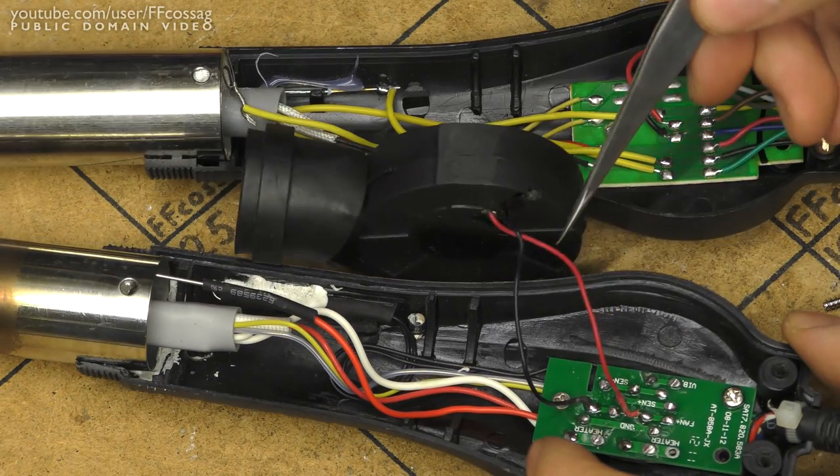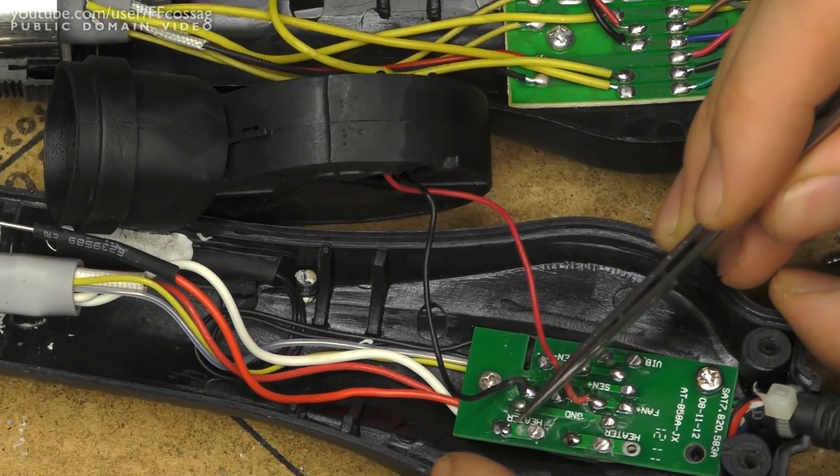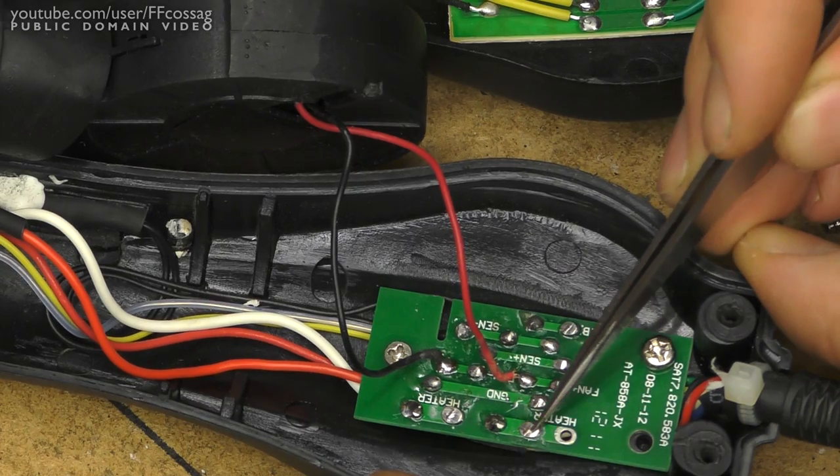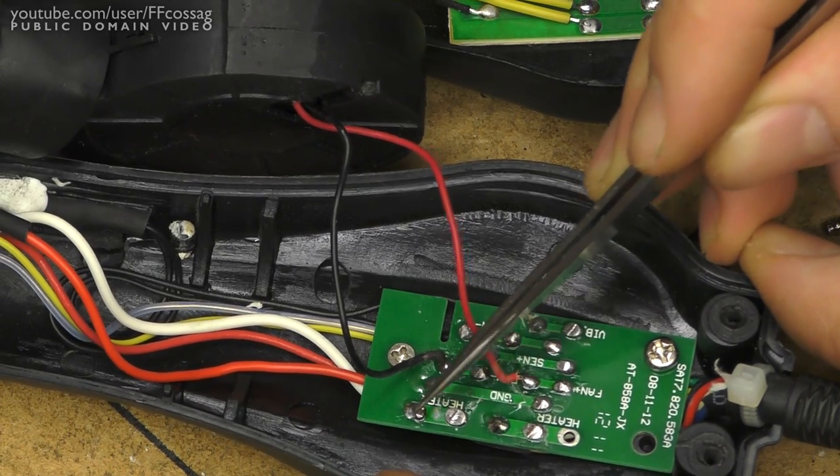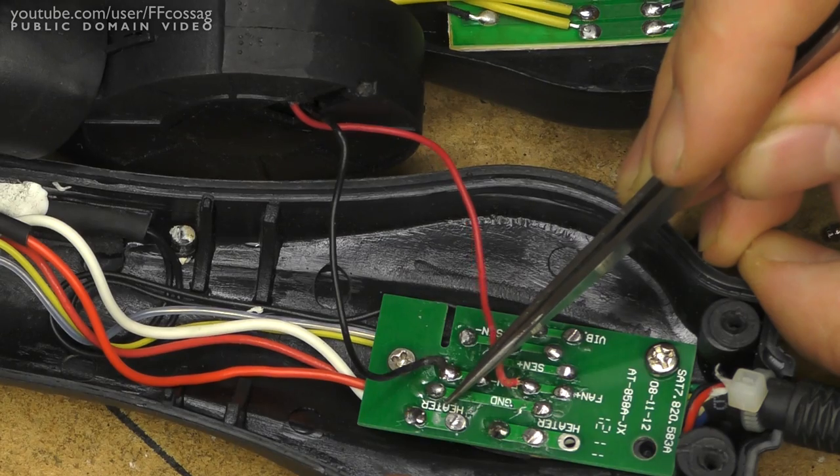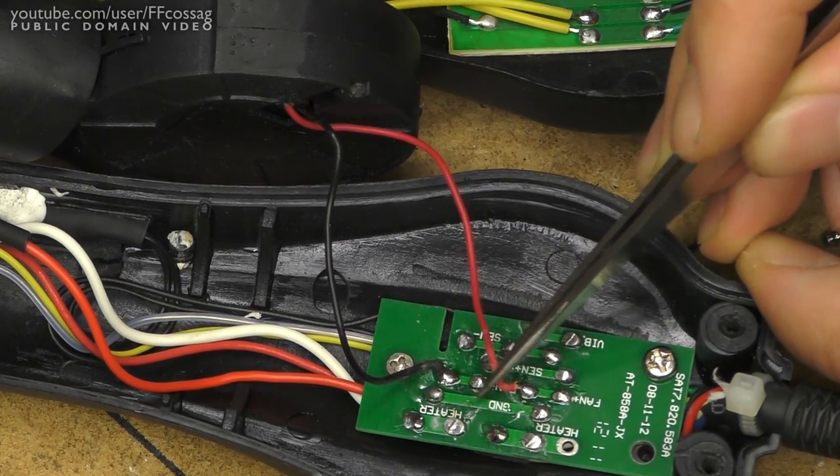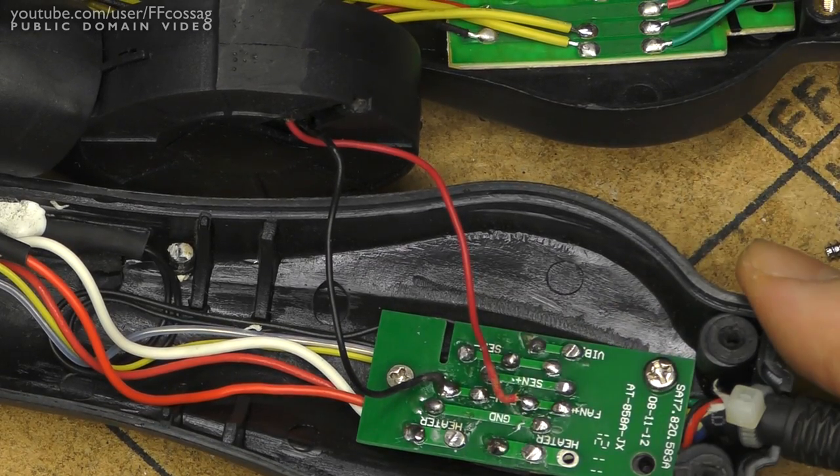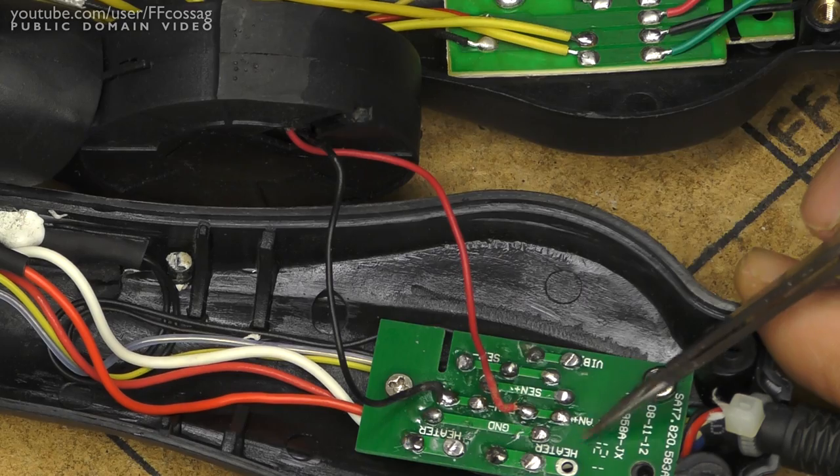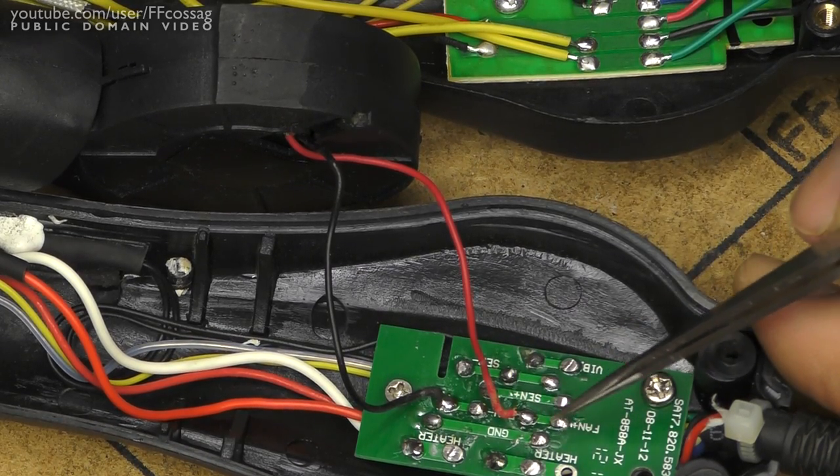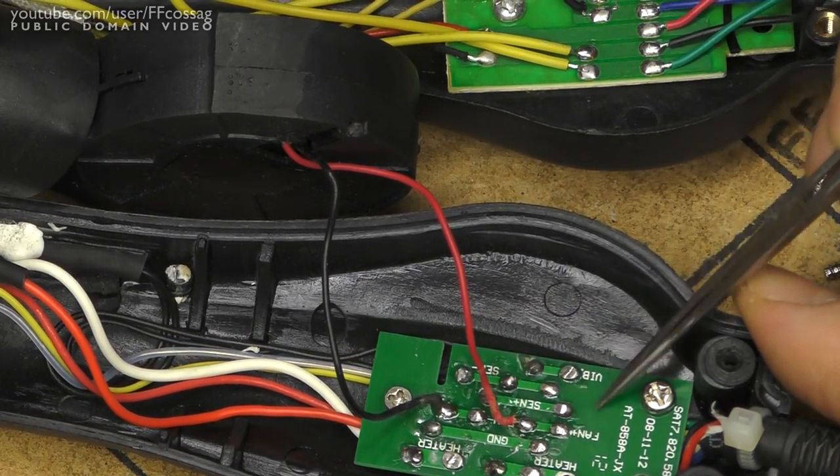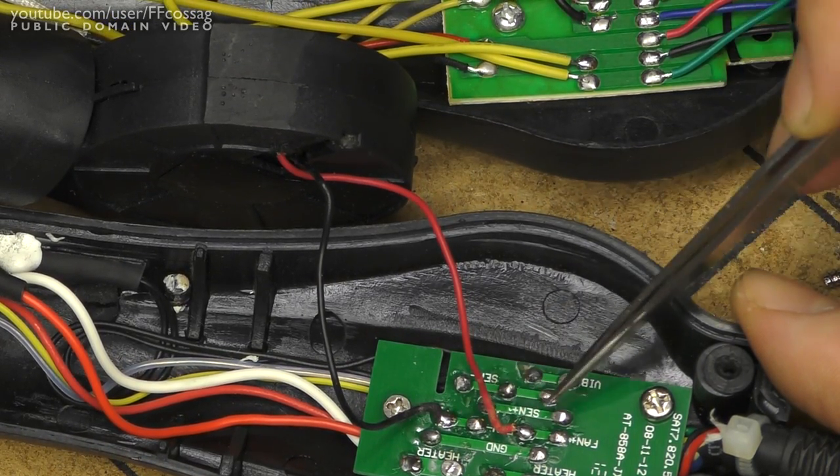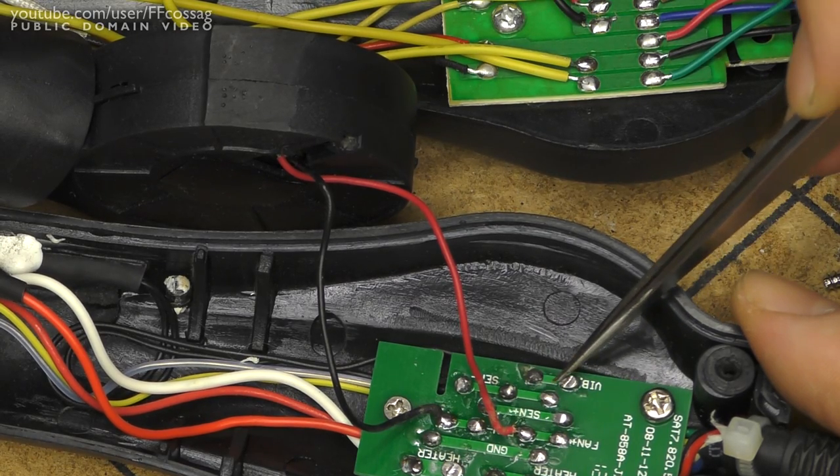Moving on, on the old one, the heater connectors are going straight to the main unit. We've got wire coming in, heater going out, wire coming in, heater going out, and beside those we have about 2mm of clearance, and then we have a large ground trace. Now it is padded with solder blobs, which is not nice, but they have gone to the effort of having fair spacing there, and ground separating the mains side from all the low voltage stuff, where we've got the 12V fan coming in, the sensing, and the magnetic switch.